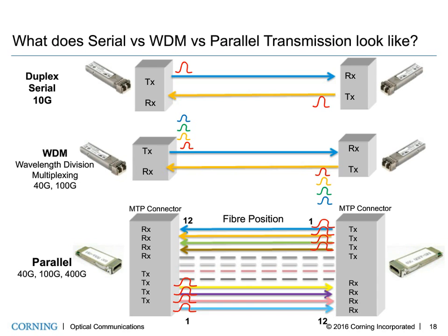So think of WDM as taking 4 independent lasers or VCSELs, operating at 4 independent wavelengths, and then combining them over a single fiber. Hugely popular in the outside plant world. Been done for a long, long time. Relatively new to be introduced into the data center space.